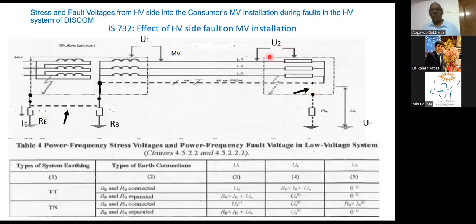This is the trend. Because of this, people are not able to connect their protective earth neutral to the supply. You can see in most locations, if they connect, some shock will come. So they will eliminate it. They don't know whether their first priority is: if I connect, I am getting shock, so let me eliminate it. This is a simple thing.